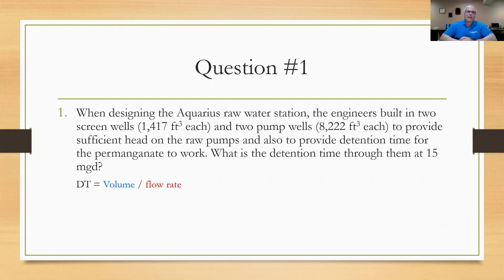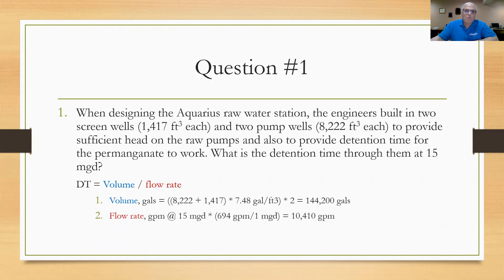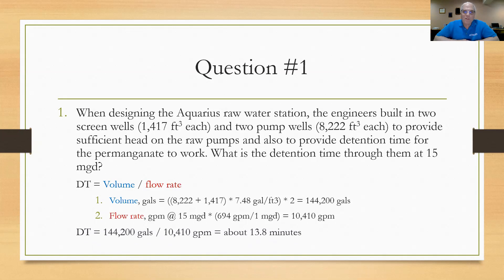This is a detention time problem: detention time equals volume divided by flow rate. First, I added the two volumes — 1,417 and 8,222 cubic feet each — converted to gallons by multiplying by 7.48, and multiplied by two for the two parallel sides, getting about 144,200 gallons. The flow rate of 15 MGD converts to 10,410 gallons per minute by multiplying by 694 GPM per MGD. Dividing 144,200 by 10,410 gives approximately 13.8 minutes detention time.